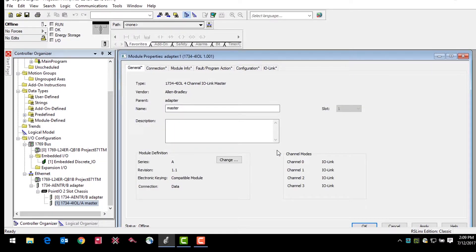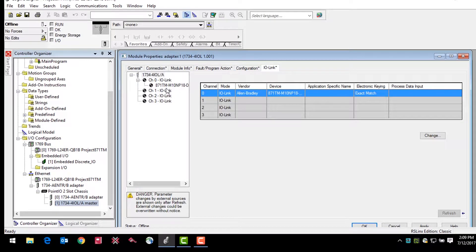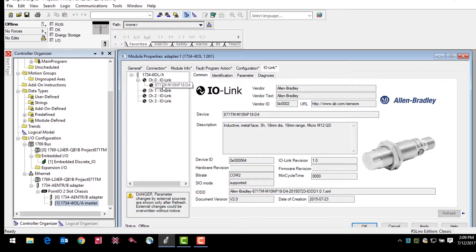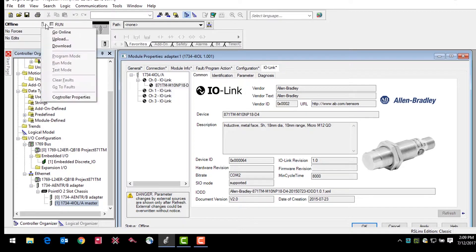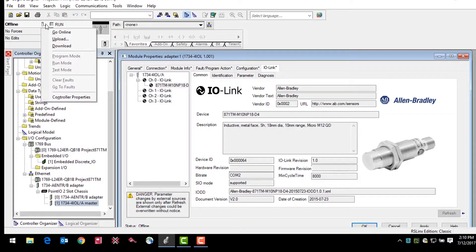Return to the IO-Link tab and select the sensor that you would like added from the organizational tree. The sensor can now be configured through the add-on profile. In a scenario where we would actually configure the sensor for an application, we would click go online at this point to communicate with the controller and sensor. For this video, we're going to remain offline and take a brief tour of the device parameters within the add-on profile.